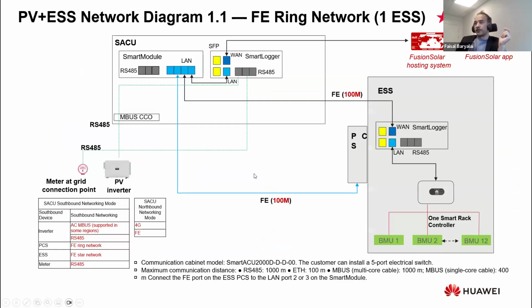So the system communication design. The PCS also has a communications line, an FE communications line, which goes from the PCS to the smart module. Later on, I will show a picture of the smart module for those who haven't seen it. But it's just an extension of the switches, the input switches, as LAN switches. So here we have SACU. Inside SACU, we have a Smart Logger 3000 and an extension switch called smart module. So the PCS will be connected directly to the LAN on the smart module.